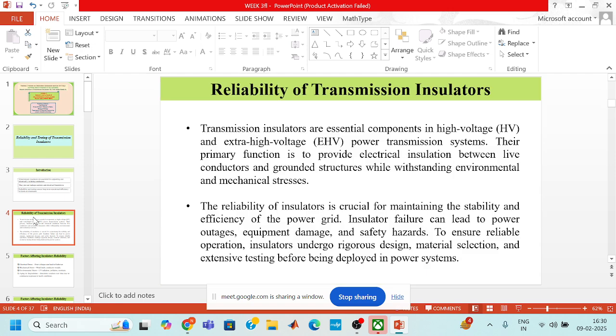As we all know, transmission insulators are a very essential component in high voltage and extra high voltage power transmission systems. Their primary function is to provide electrical insulation between live conductors and grounded structures while withstanding environmental and mechanical stresses. So basically, reliability of insulators is very important for maintaining the stability and efficiency of the power grid.